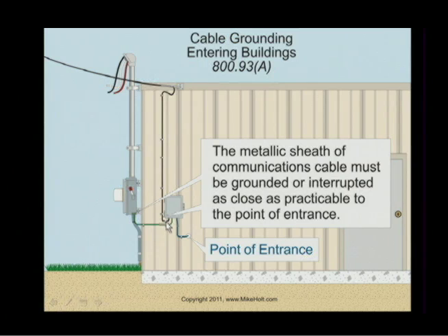Once we get into the next slide, we're going to focus on this bonding conductor because, starting in the 2005 code, an inter-system bonding terminal is required. Now you had millions of buildings built before the inter-system bonding terminal — 250-94 — and whenever you had to make connections there, you had to try to find an electrode or a grounding electrode conductor and go that direction.